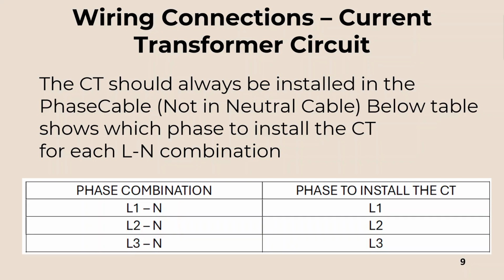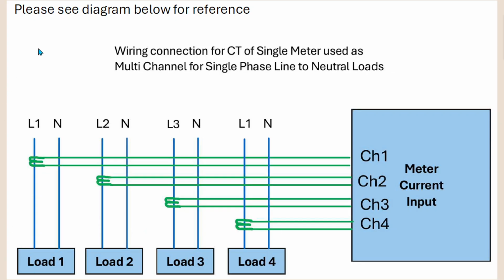The table below shows where you will install the CT. For line 1 to neutral, you have to install the CT in the phase cable. For line 2 to neutral, you have to connect the CT in line 2, which is the phase cable, same as for L3. An example for the line-to-neutral loads is shown here. Load 1 is line 1 to neutral, load 2 is line 2 to neutral, load 3 is line 3 to neutral, load 4 is line 1 to neutral.